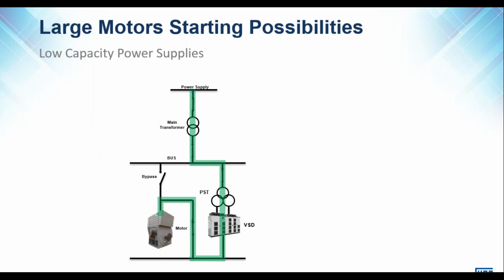So one practical application for this would be if you are using a VSD to start a motor that does not necessarily get to its full torque at the end of acceleration. It was the blue curve that I showed earlier. And it is theoretically possible to put a VSD in circuit that is smaller than the rating of the motor, just to get the motor up to speed, and then bypass the VSD before the full load is applied.